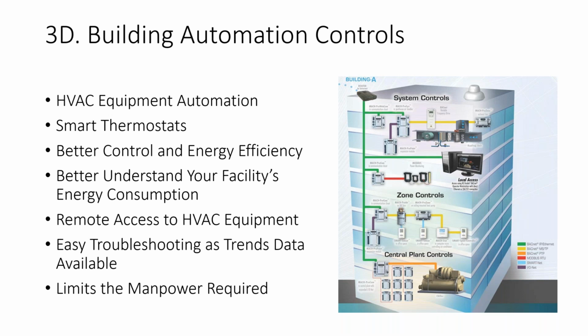I will explain a couple more good things about building controls. They help us to remotely access HVAC equipment and to troubleshoot the equipment. The trend data is available. We can see at what speed the fan, the motor, and the chiller were running, and what caused the problem. We can review the trend data and make adjustments to our systems. And lastly, it limits the manpower required to operate that big plant, and we can make our systems efficient by bringing the operating cost low with minimum manpower.